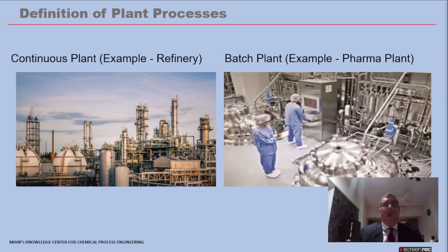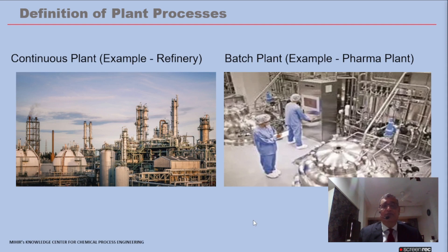We start with the definition of plant processes: a continuous plant such as a refinery, and a batch plant such as a pharmaceutical or small-scale industry plant. In a batch plant — for example a polymerization or pharmaceutical plant — batch reactions occur in the reactor, additives must be dosed batch-wise in a particular sequence, and this sequence must be captured in the notes section of the P&ID. In a continuous plant like a refinery, such notes may not be required since the plant operates 24 hours continuously.